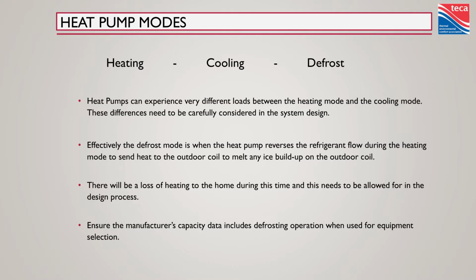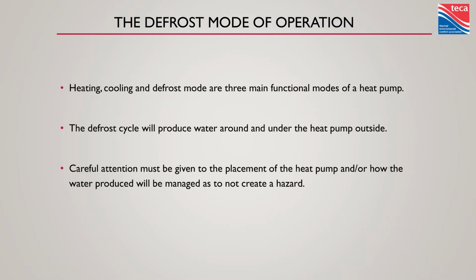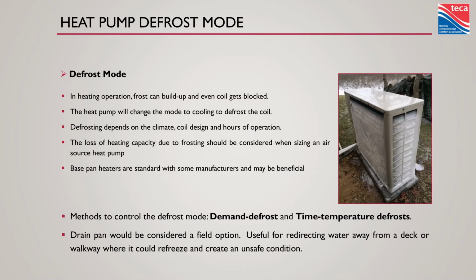We're not trying to pump heat out of the space, we're actually just trying to melt the ice that's right on that coil. But when it does that, there's 2 things to remember. One, that water's got to go somewhere, so hopefully it's not running across a pathway and refreezing, creating a slipping hazard. So think about that when you place your heat pump. But also, as it reaches the end of a defrost cycle, some of that water is going to vaporize, turn into steam. I have more stories than I have fingers to count them on of homeowners thinking their heat pump is on fire and calling the fire department. So make sure that you're talking to your clients about this. Tell them this is normal. It's something to understand that is going to happen.